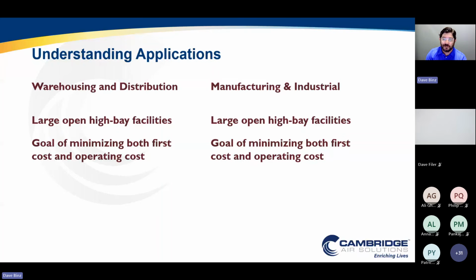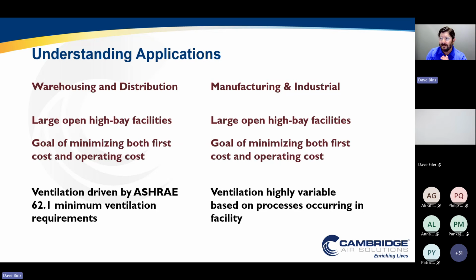Uniquely, both warehouse and distribution and manufacturing want to minimize first costs and minimize operating costs, right? Both these types of buildings and operations are trying to balance investments in their HVAC against investments in their operations. And that can often be a tricky scenario when we're trying to recommend HVAC solutions. But when it comes down to the HVAC system, one of the biggest differences between these two facility types is how we are dealing with ventilation. In warehouse distribution, most of the ventilation is driven by your ASHRAE 62.1 minimum ventilation requirements, which can be fairly low for a large open space. There's also some infiltration that we'll talk about a little bit later.